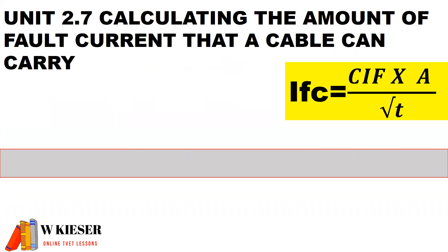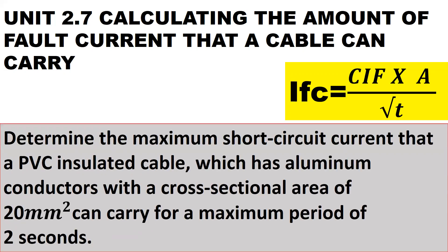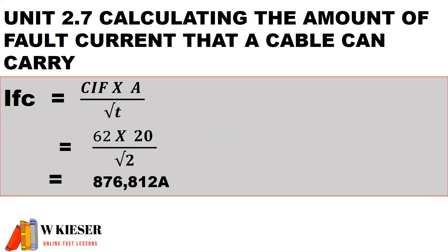Calculating the amount of fault current that a cable can carry. The formula: I_FC is the fault current, A is the cross-sectional area in mm², CIF is the conductor insulation factor, and T is the time in seconds. Determine the maximum short circuit current that a PVC insulated cable with aluminum conductors and a cross-sectional area of 20 mm² can carry for a maximum period of 2 seconds. The conductor insulation factor is 62, the cross-sectional area is 20 mm², and the time is 2 seconds. Therefore, the fault current is 876,812 amps.